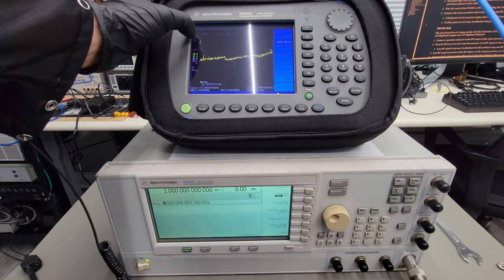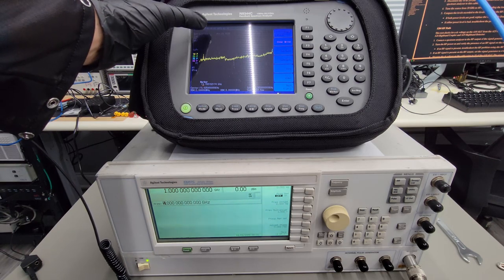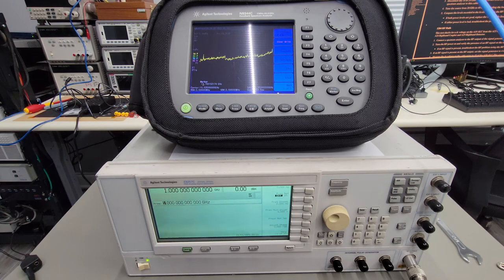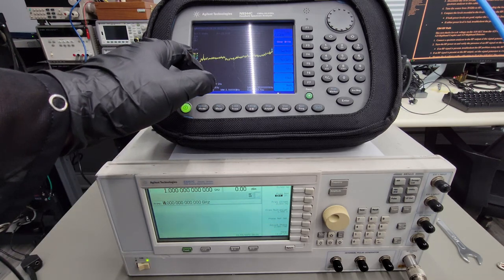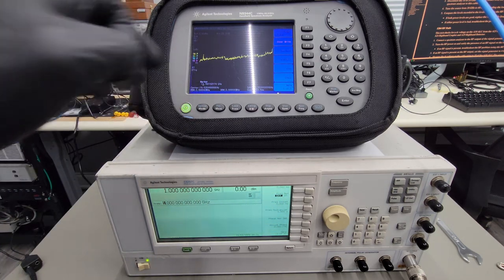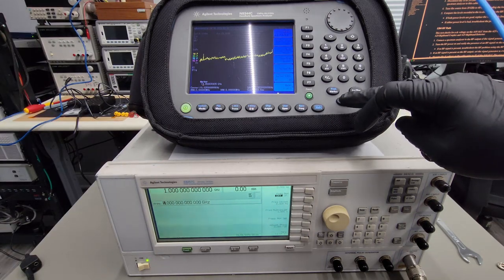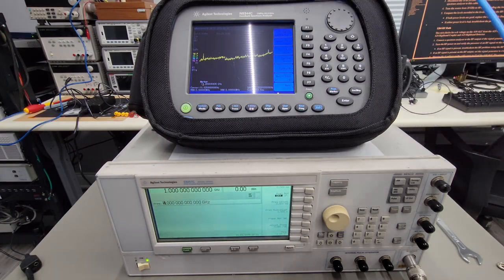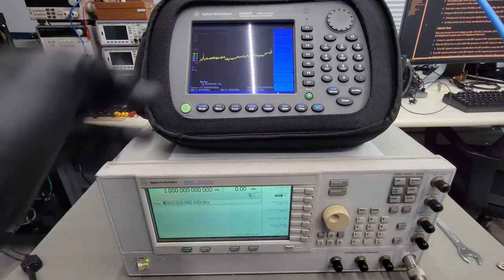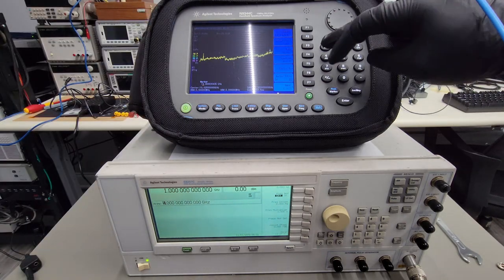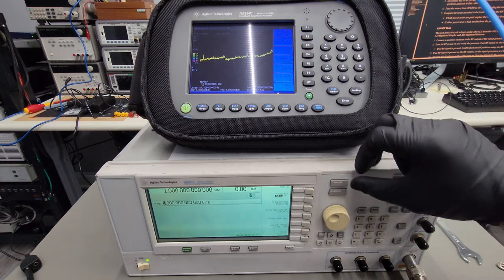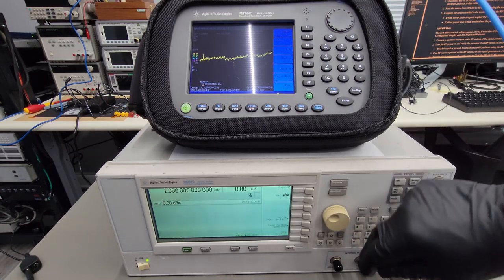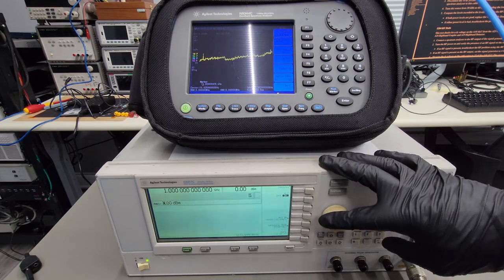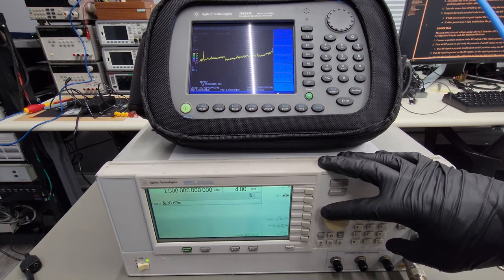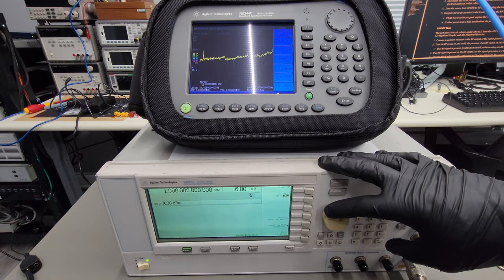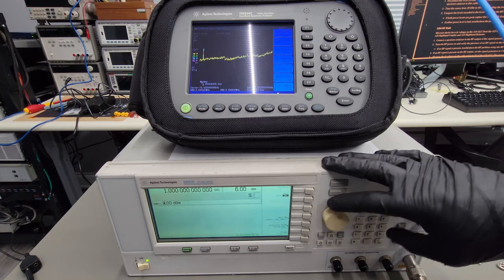This is minus 5 dBm here, this line. So our reference level is 5 dBm at the top of the chart. And you can see we do have a signal approximately at 1 gigahertz here, but it is quite small. So if I do a peak search, right now the noise at the 20 gigahertz end of the spectrum is actually higher than this peak. So maybe I have to increase the power a little bit on the signal generator here. And now we're starting to see the peak.